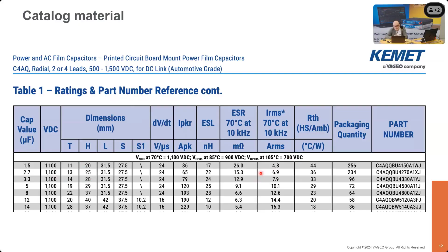You probably switch at 50 kilohertz or 30 kilohertz, whatever, and your temperature is probably not 70, it's about 80, 85, or 90 - so what will be the impact for you? Also keep an eye on voltage derating - there's some room for shifting the rated voltage, or vice versa. You cannot use the component at its rated voltage at higher temperature, so you have to derate. For example, at 70 degrees you have 1100 volts, at 85 it's only 900 volts, and at 105, the maximum temperature, you end up with 700 volt DC. Something that looks simple at first turns out to be pretty time consuming when figuring out the right component.